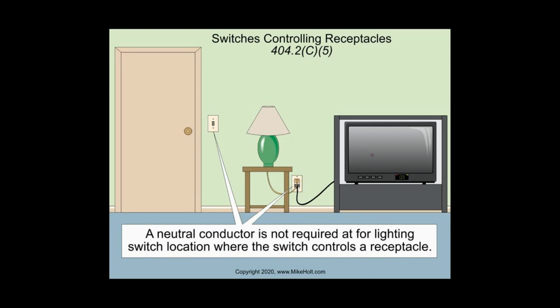Switches controlling receptacles, 404.2(C)(5). A neutral conductor is not required for lighting... I apologize. A neutral conductor is not required for a lighting switch location where the switch controls a receptacle. The slide is written wrong. That's half my problem here. The whole point is you don't need a neutral at this switch because you're just switching a half hot. Not really a big deal.